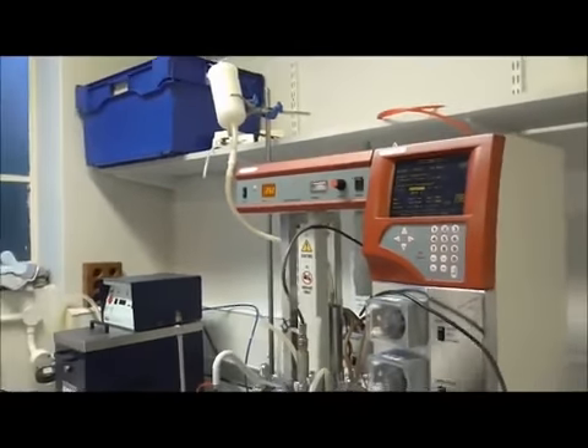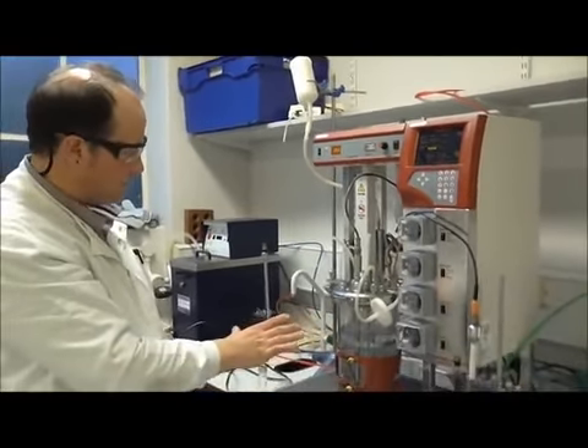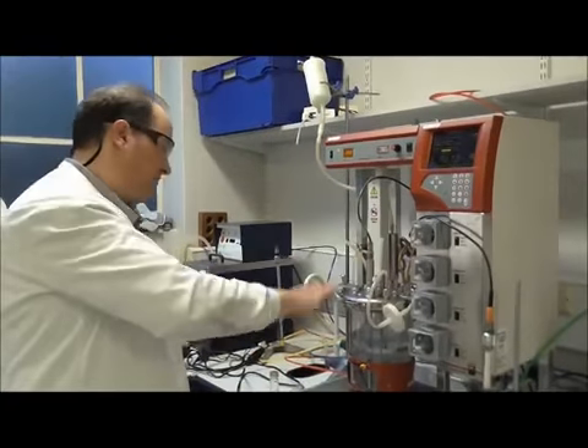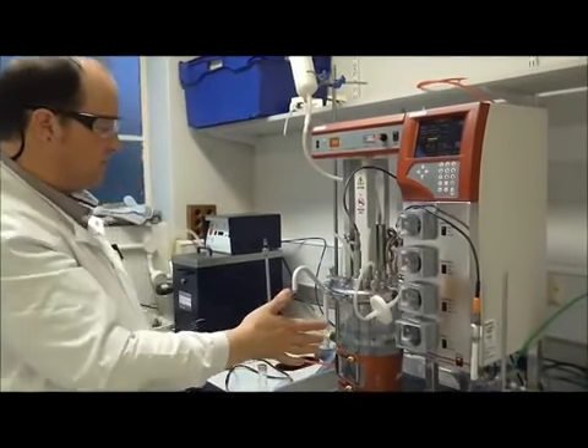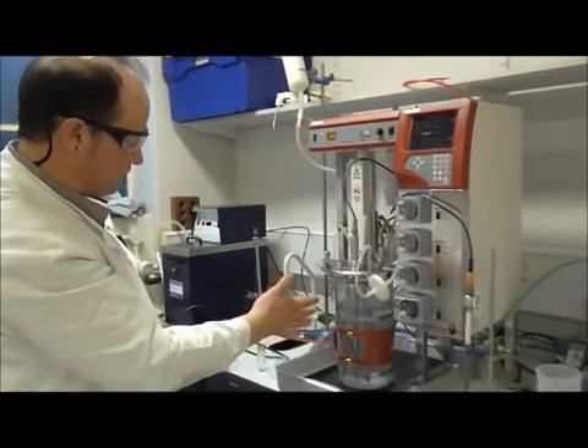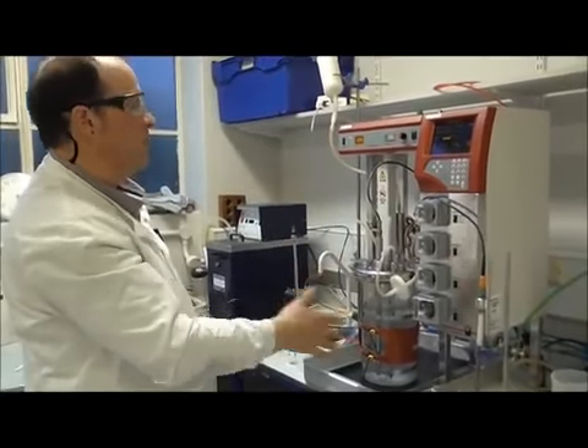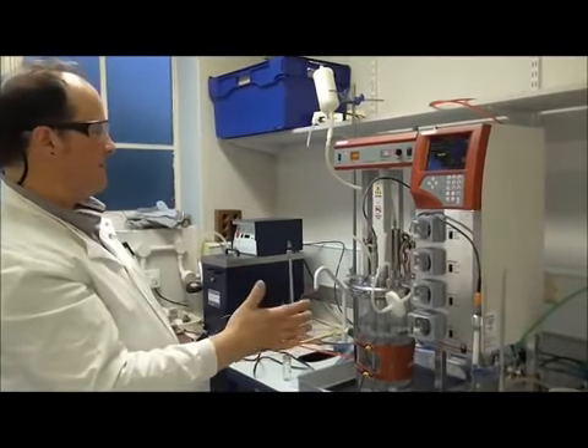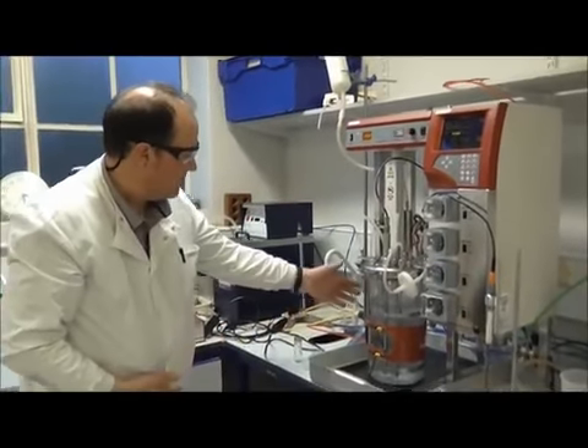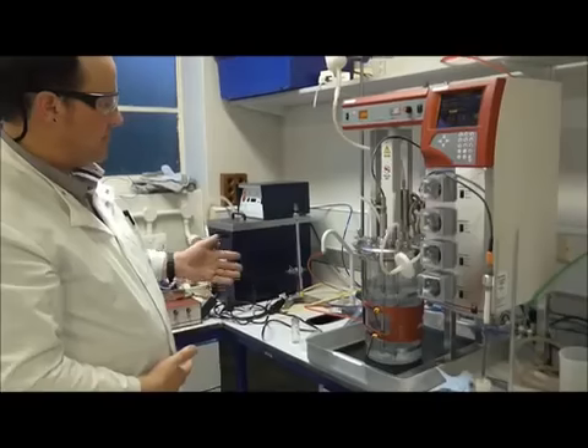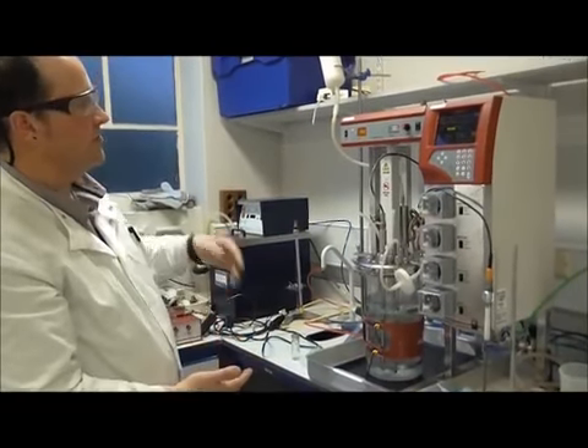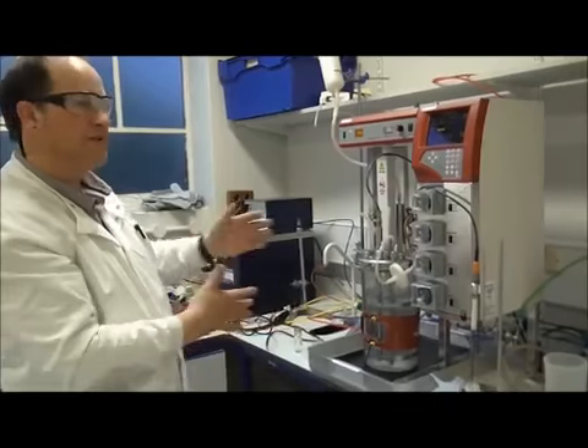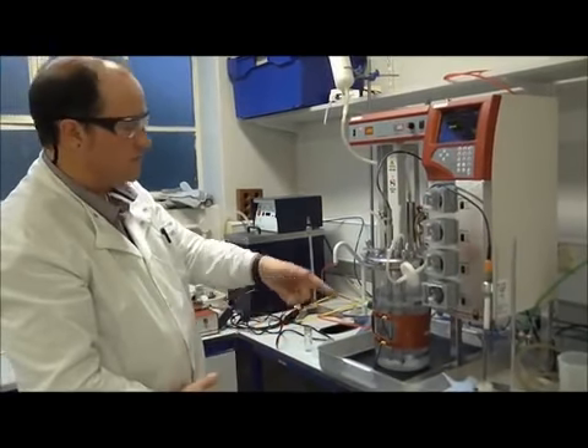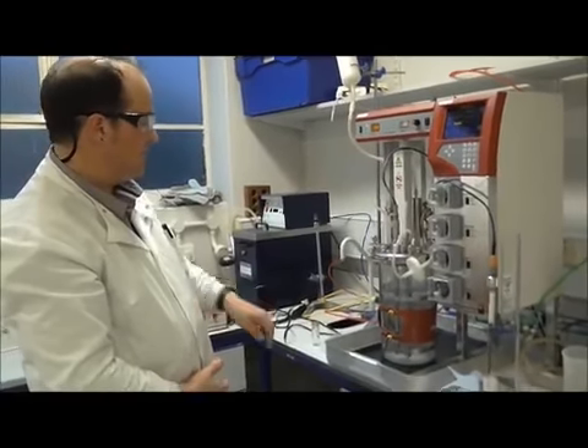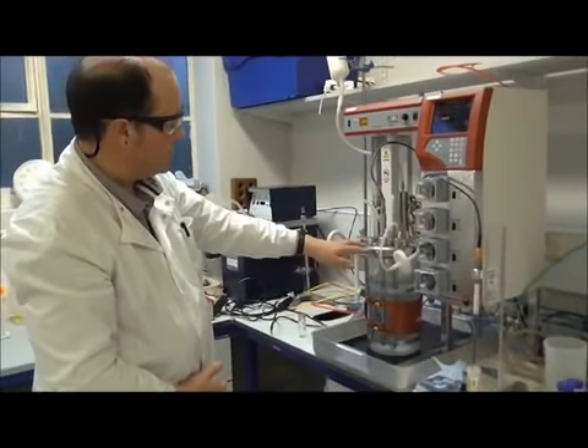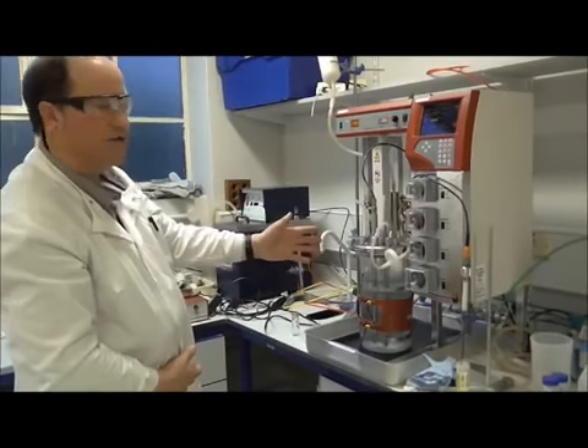Ordinarily you would calibrate both probes prior to setting up the vessel. Once the vessel has been autoclaved, you set it back up on the rig again, and it's running at your operating temperature. You can calibrate the pH probe again by taking a sample out, check that on a bench meter, and does the bench meter reading correspond to the reading you're getting on here? If they are one and the same, all well and good. If not, then we can sort of tweak the gain to suit.